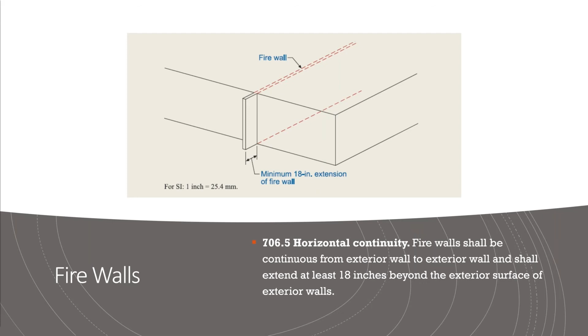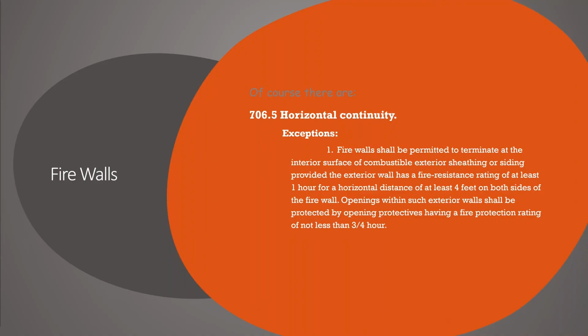Exception 1 is firewalls shall be permitted to terminate at the interior surface of combustible exterior sheathing or siding, provided, and yes, I'm saying these words specifically when I say and, provided, or, these are big words in the code. So again, provided the exterior wall has a fire resistance rating of at least 1 hour for a horizontal distance of at least 4 feet on both sides of the firewall. Openings within such exterior walls shall be protected by opening protectives having a fire protection rating of not less than 3/4 hour. So what does that look like?